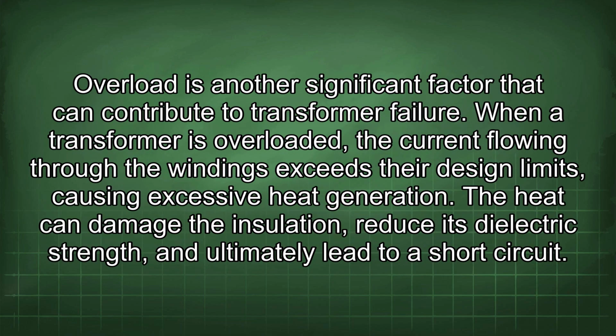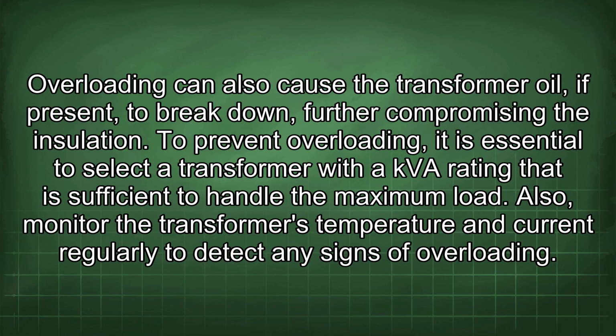Overload is another significant factor that can contribute to transformer failure. When a transformer is overloaded, the current flowing through the windings exceeds the design limits, causing excessive heat generation. The heat can damage the insulation, reduce its dielectric strength, and ultimately lead to a short circuit. Overloading can also cause the transformer oil, if present, to break down, further compromising the insulation.